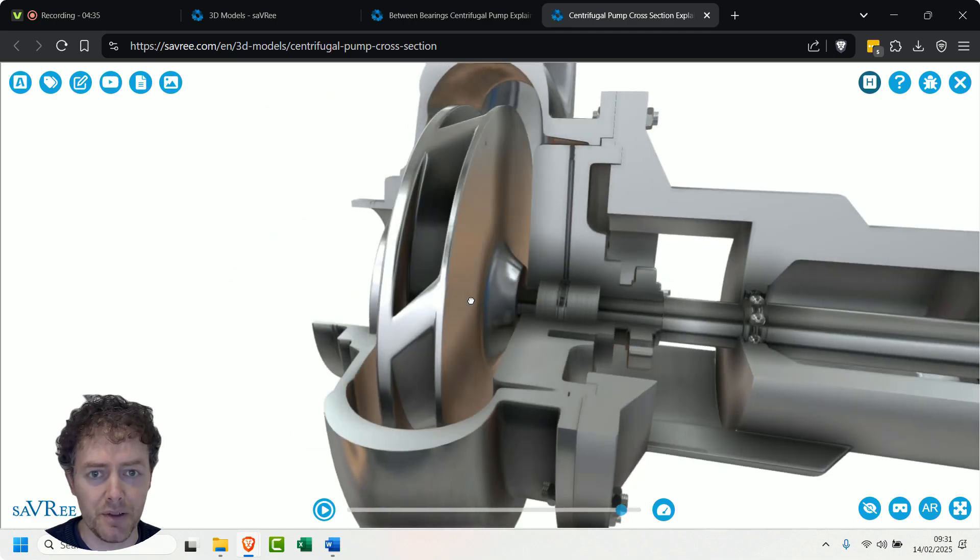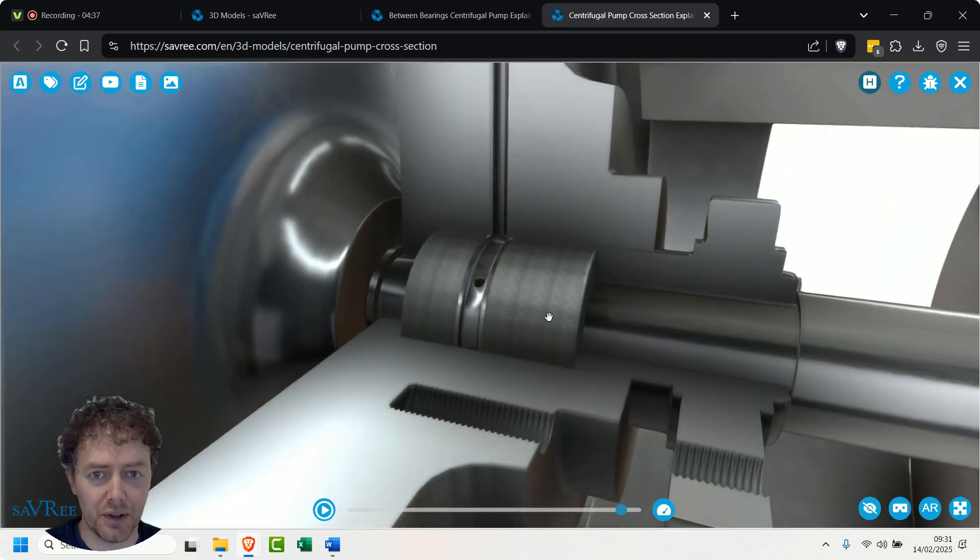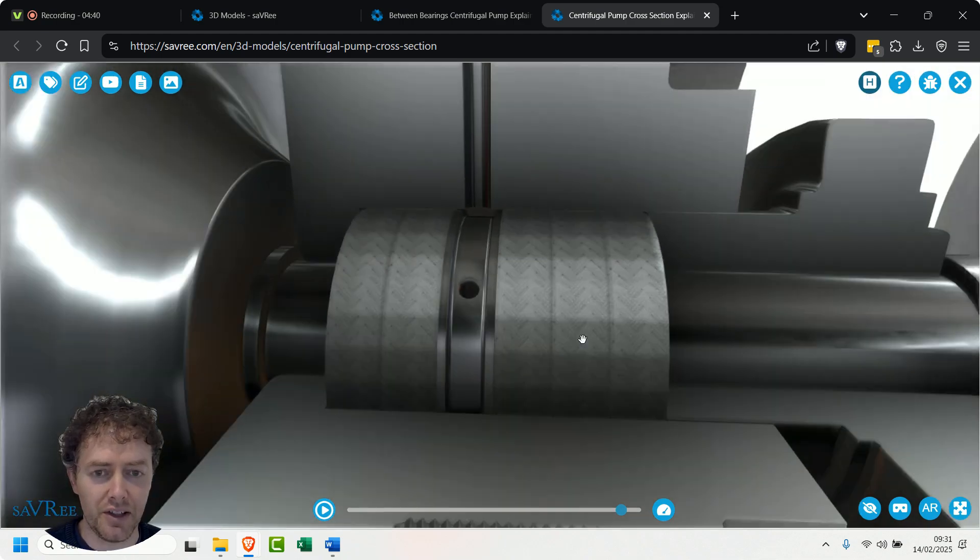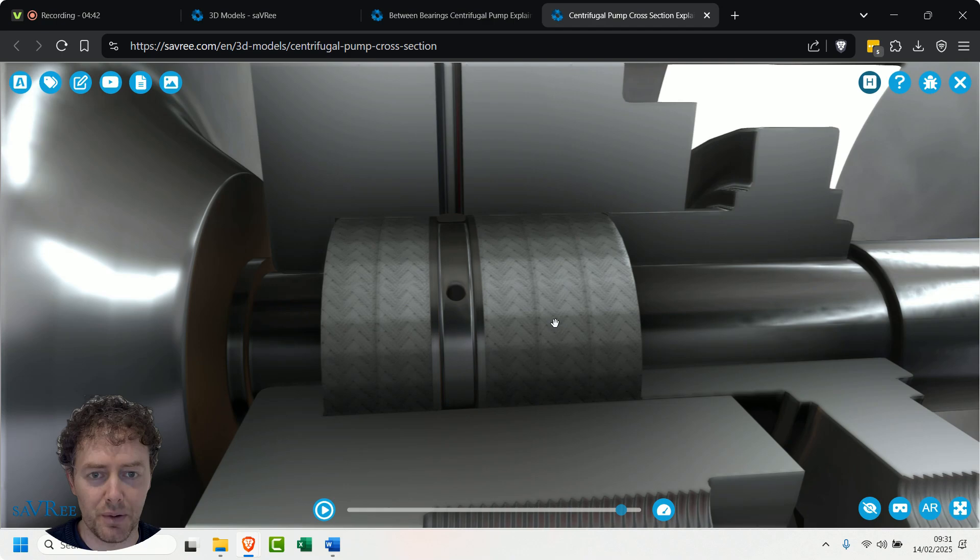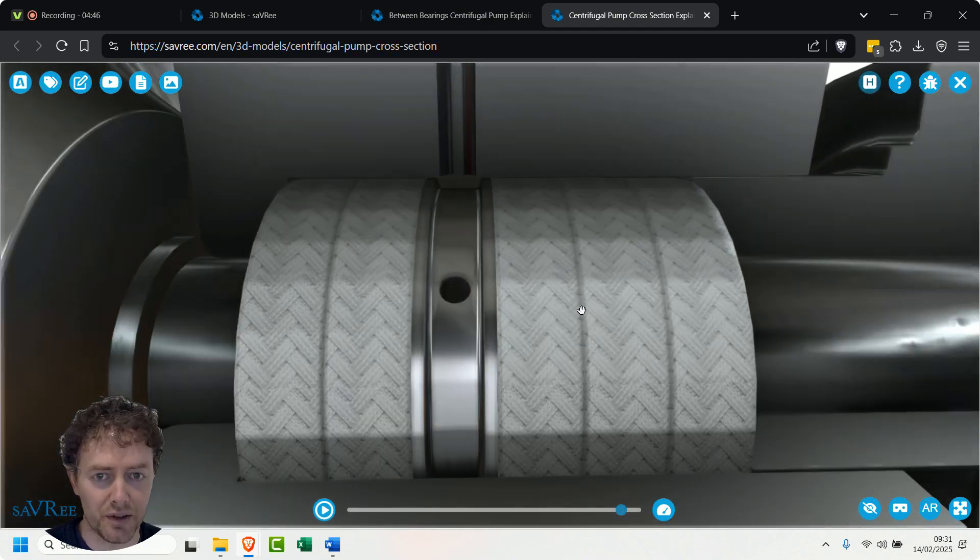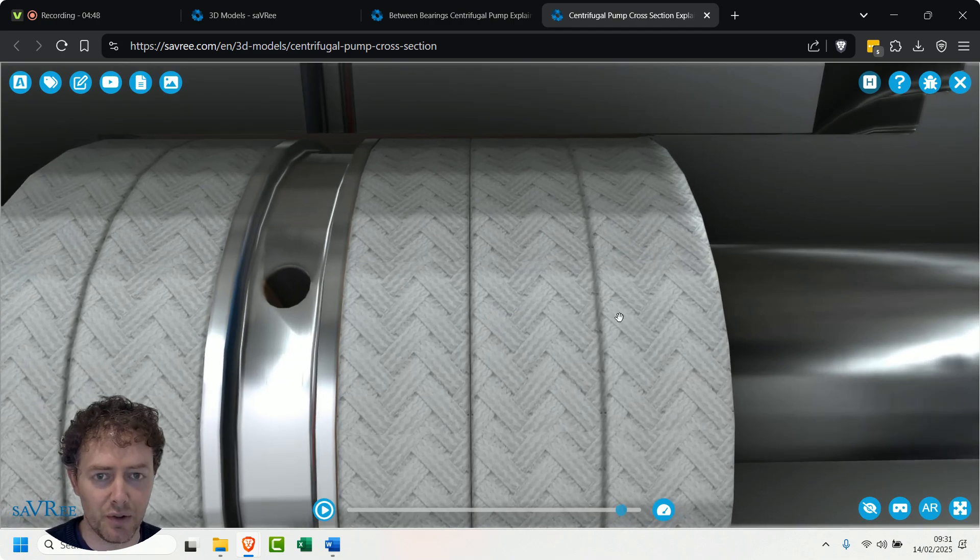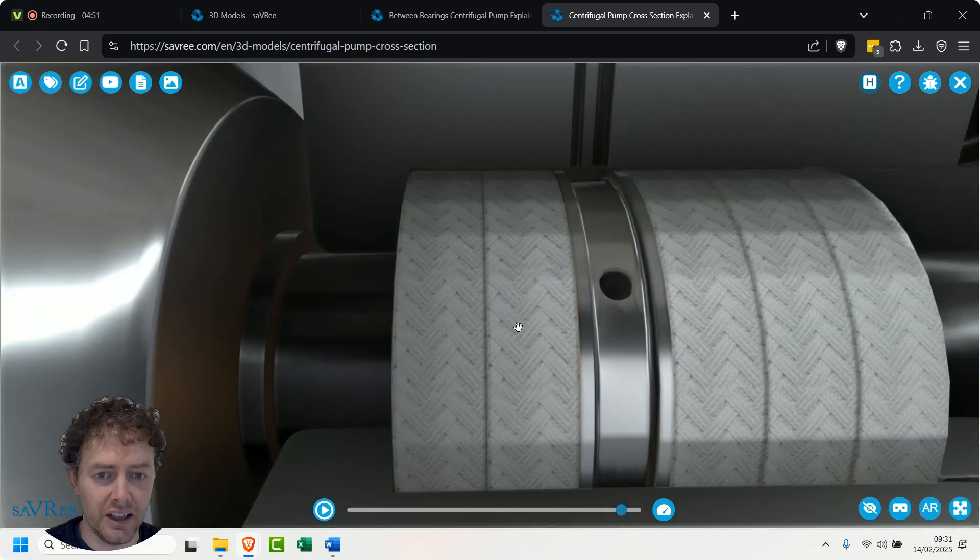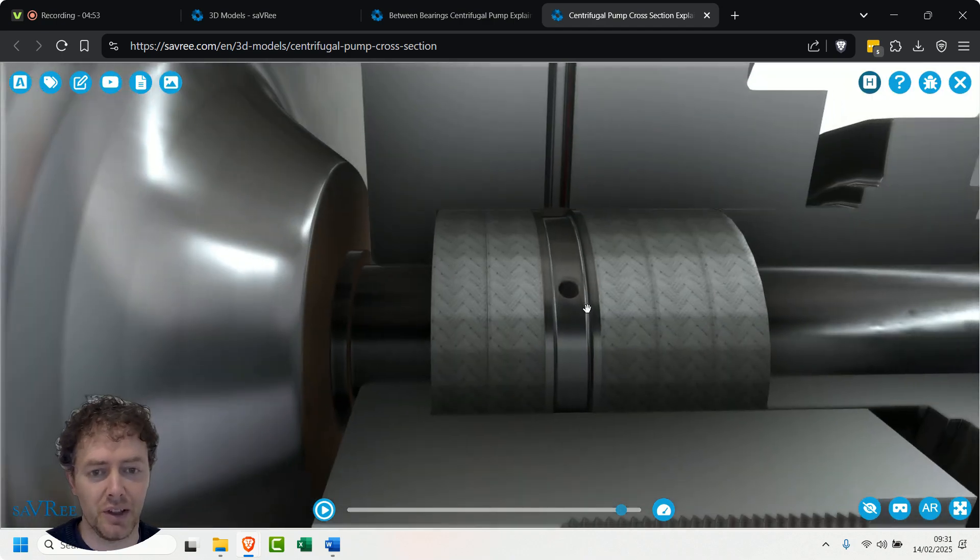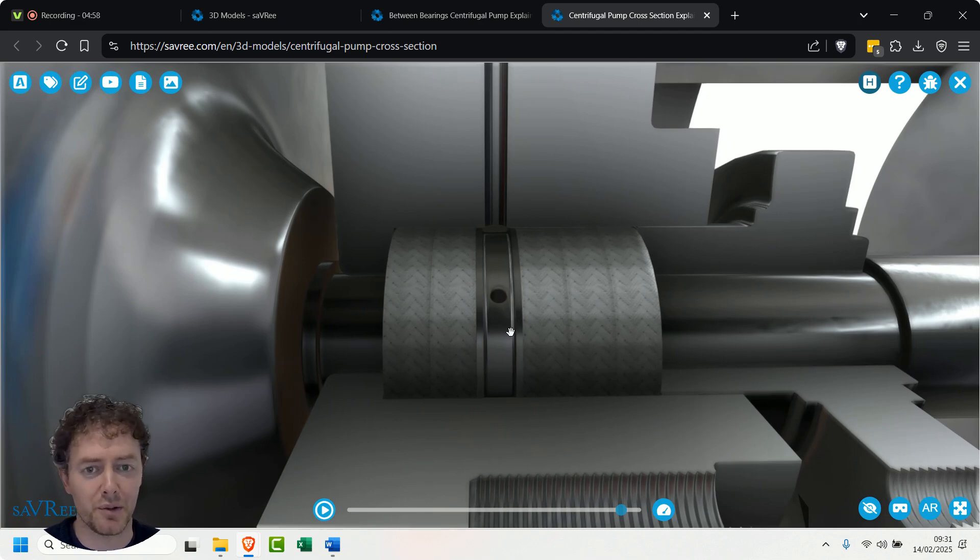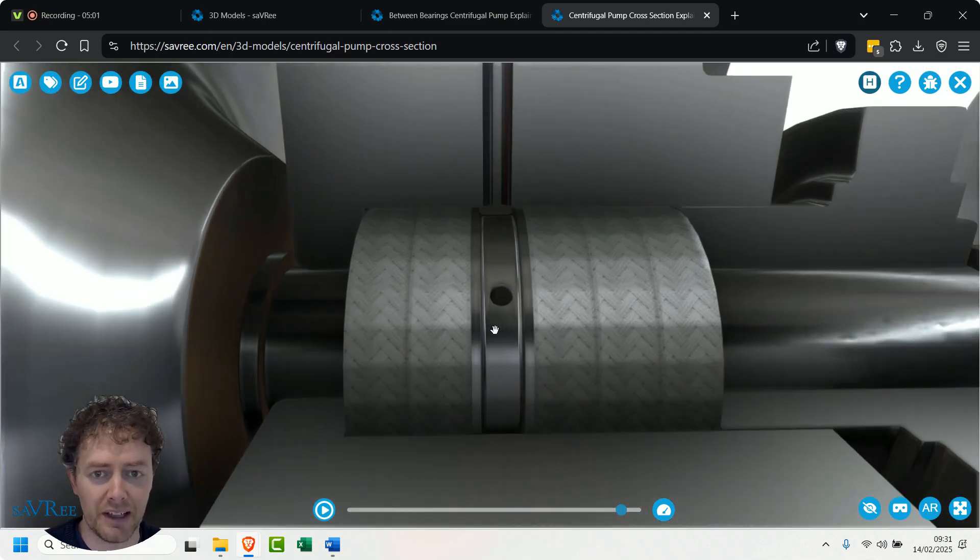So sealing arrangement is this here. This whole arrangement sits within what's called a stuffing box. We've got packing - it's this rope kind of stuff here, the bit that looks like rope. It's on this side and it's also on the other side here - that's packing material. What it'll be is it's kind of like rope, but what happens is you take the rope and sometimes you'll cover it in some sort of lubricant, and you'll wrap it around in this space within the stuffing box.